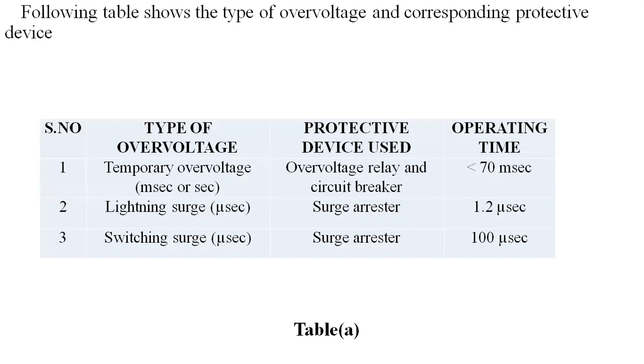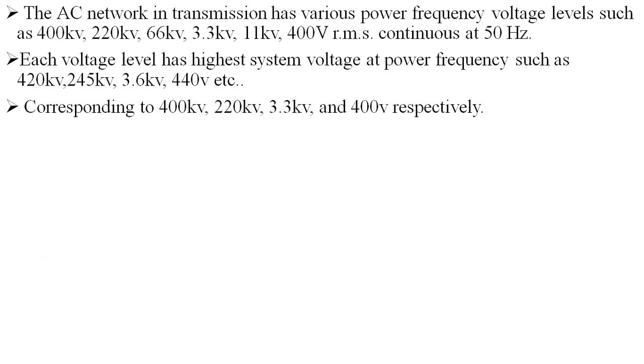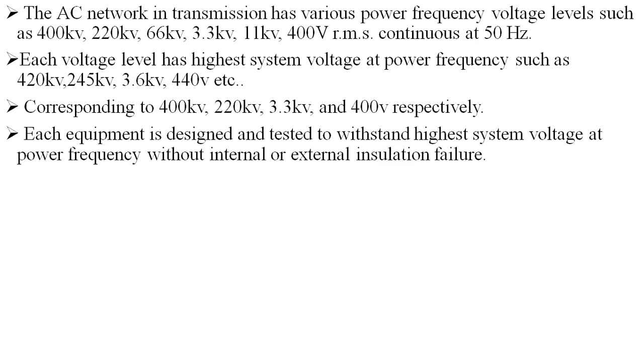The AC network in this transmission has various power frequency voltage levels such as 400 kV, 220 kV, 66 kV, 3.3 kV, 11 kV, and 400 volts RMS continuous at 50 hertz. Each voltage level has a highest system voltage at power frequency such as 420 kilovolts, 245 kilovolts, 3.6 kilovolts, 440 volts, etc., corresponding to 400 kilovolts, 220 kilovolts, 3.3 kilovolts and 400 volts respectively. Each equipment is designed and tested to withstand this highest system voltage at power frequency without internal or external insulation failure.